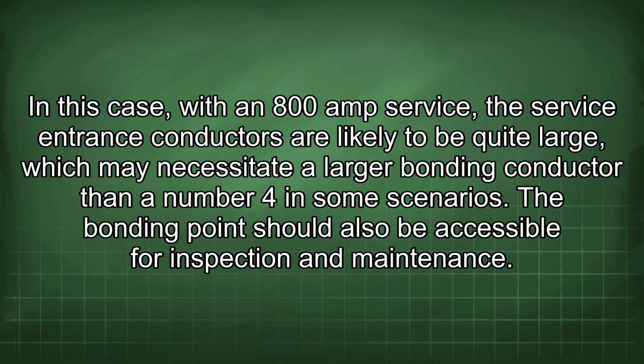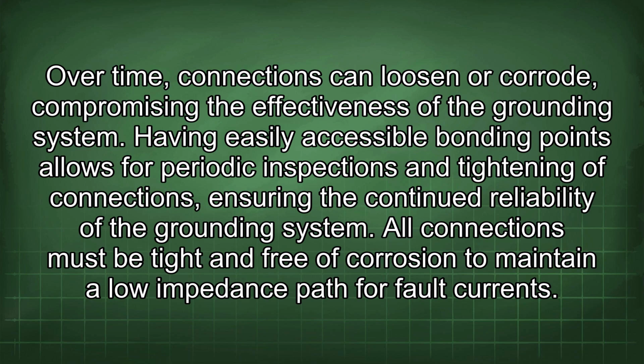The bonding point should also be accessible for inspection and maintenance. Over time, connections can loosen or corrode, compromising the effectiveness of the grounding system. Having easily accessible bonding points allows for periodic inspections and tightening of connections, ensuring the continued reliability of the grounding system. All connections must be tight and free of corrosion to maintain a low impedance path for fault currents.